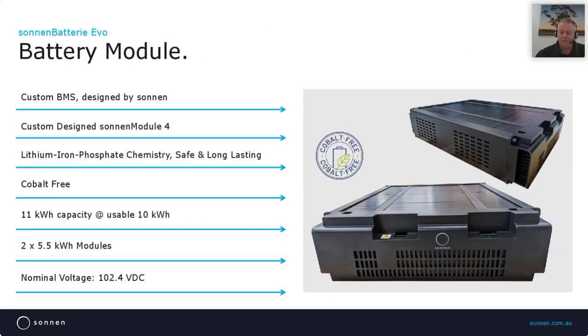Custom Sonnen Module 4 battery modules with custom BMS designed by our Sonnen R&D team in Germany. We continue the Sonnen tradition of using safe, long-lasting LFP chemistry, which is cobalt-free. Cobalt is a toxic metal that can be mined unethically and reduces the recyclability of battery cells. Each module has a capacity of 5.5 kilowatt hours, giving the sonnenBatterie Evo a usable capacity of 10 kilowatt hours. Each module has a nominal voltage of 102.4 VDC, paired in series, giving the system a total nominal voltage of 204.8 VDC.